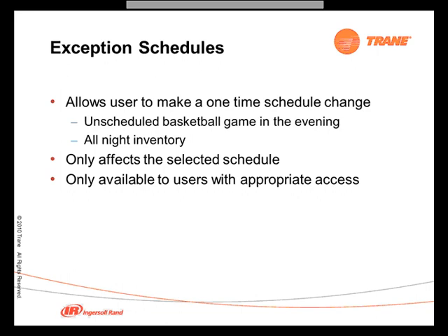Exception schedules. Exceptions, as I mentioned before, are a little bit different. Exceptions typically will take precedence over anything that's on the schedule, up to and including holidays. So exceptions sit at the very top. They have the highest priority. If you have a regular scheduled day where the store is normally supposed to be occupied, you go in, create a holiday, unoccupy the store, and then later on decide to throw a party, you throw a party by creating an exception schedule. The exception schedule rules over a holiday and over an HVAC schedule type.